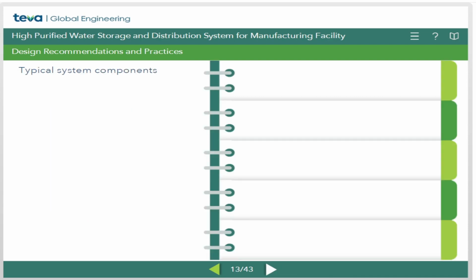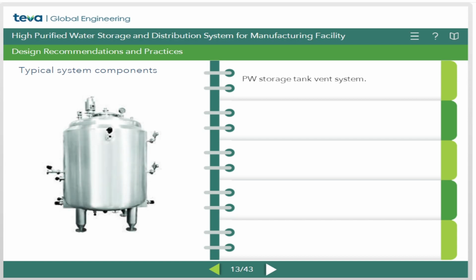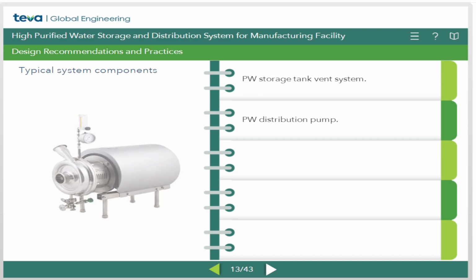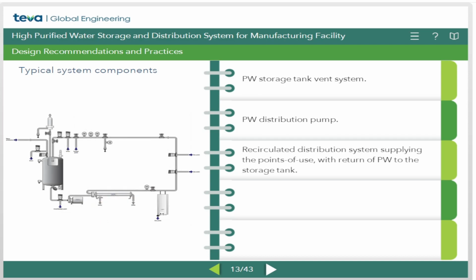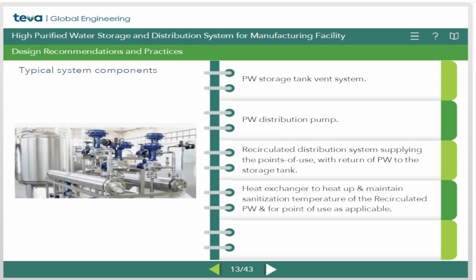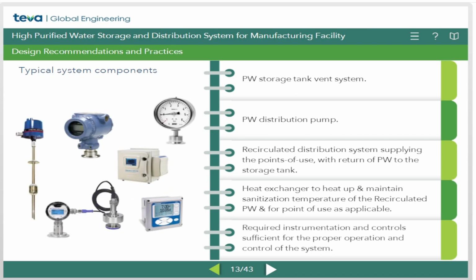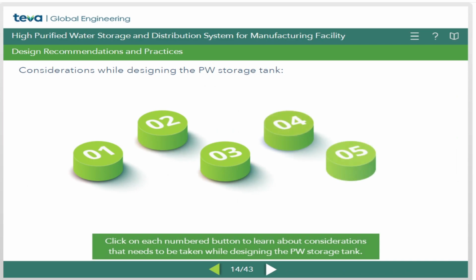Typical system components consist of purified water storage tank with vent system, purified water distribution pump, recirculated distribution system supplying the points of use with the return of purified water to the storage tank, heat exchanger to heat up and maintain sanitization temperature of the recirculated purified water, and for point of use as applicable. Required instrumentation and controls sufficient for the proper operation and control of the system. Click on each numbered button to learn about considerations that need to be taken while designing the purified water storage tank.